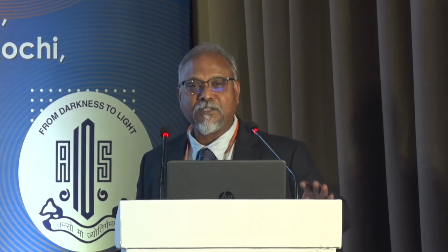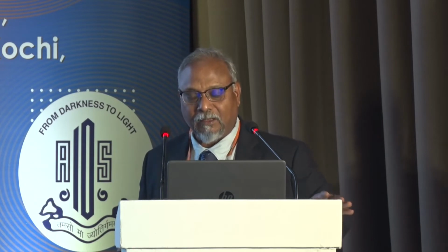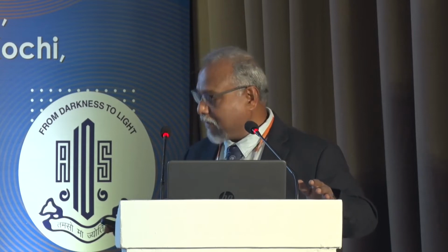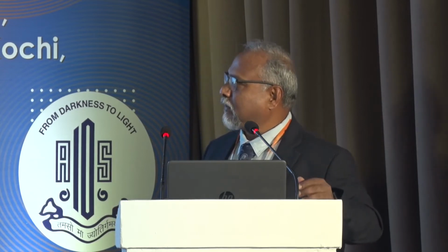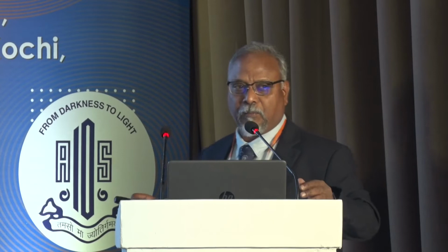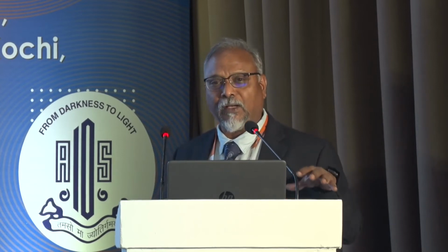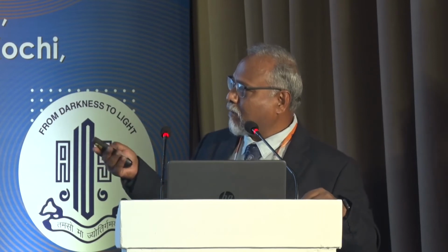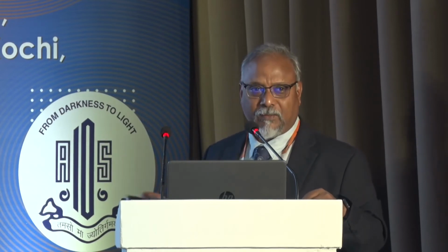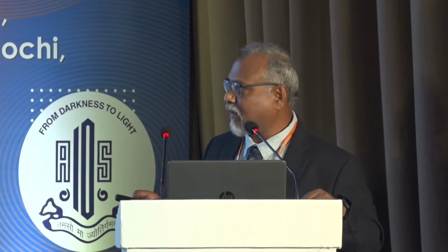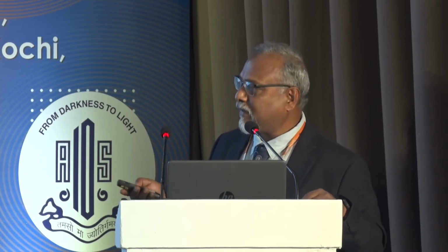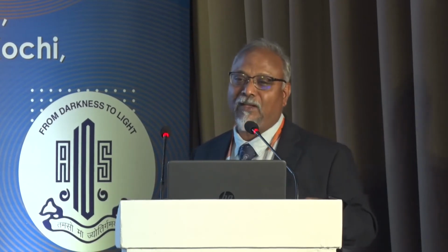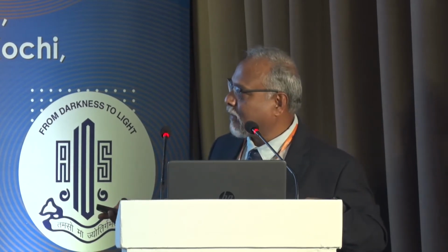The third thing it does is bend. It bends light. So this bending is controlled by the width of the ridges. Okay, so it's as simple as this. So when this cross section of a diffractive plate, which is simply put on a monofocal lens, constitutes a bifocal IOL or multifocal IOL. And the way light behaves after passing through it will largely depend on the height and the width of the diffractive ridges. Now, it's very, very interesting to note that the height of the ridges were based on the fovea sensitive wavelength of light, which is 550 nanometers.